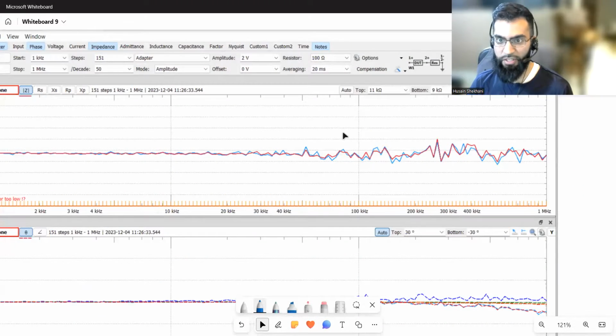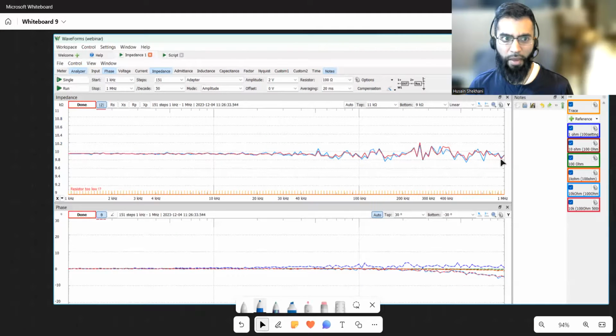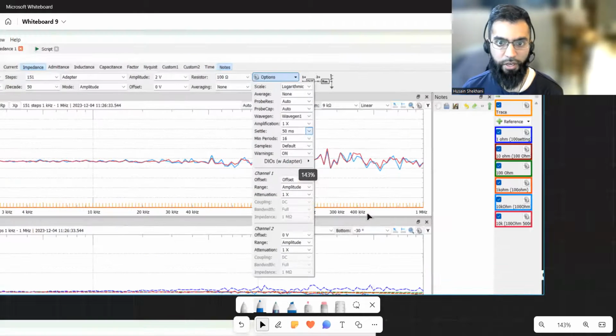We do have a little bit of noise, you might say, or this is sometimes bias from the calibration procedure, where the signal is not very large for short circuit or open circuit, so you have error in that result just due to how small the signal is. But it doesn't get anywhere near plus or minus 5%, even up to 100 kilohertz or up to 1 megahertz. It's not even 5% off. So one could say that we can measure 10 kilohms in this setting all the way up to 1 megahertz at least. This device goes up to 10 megahertz. I don't evaluate that high, but whatever settings are important for you, you should evaluate there. I'm just working in general settings.